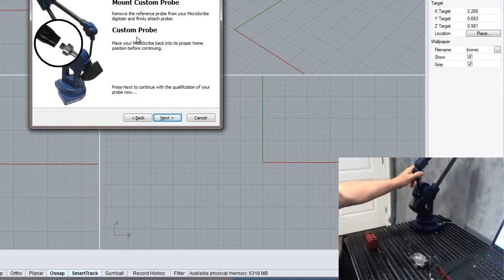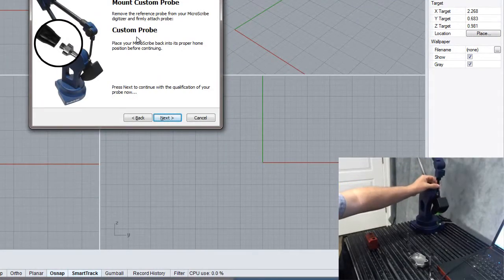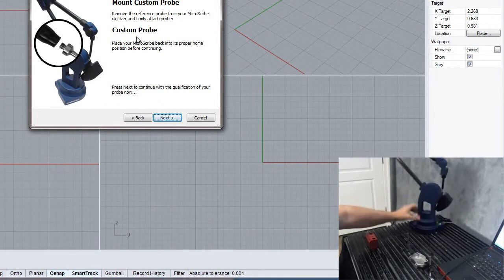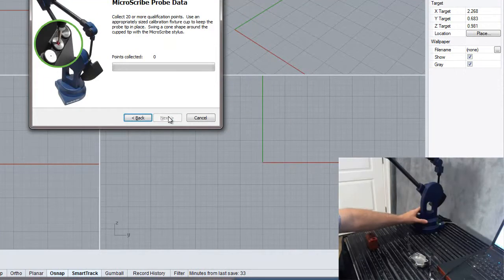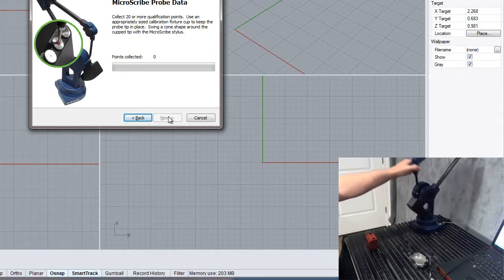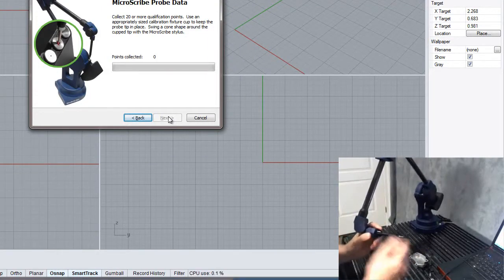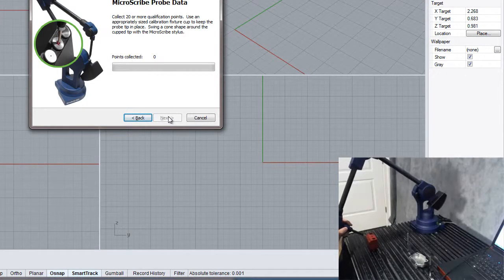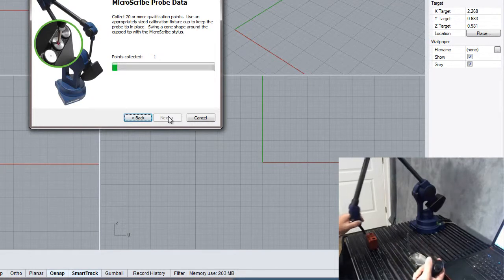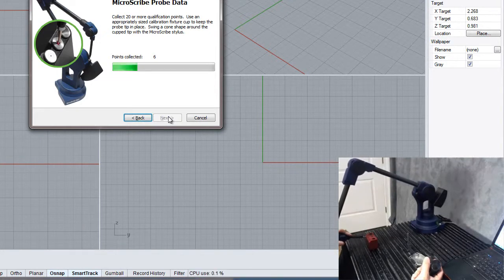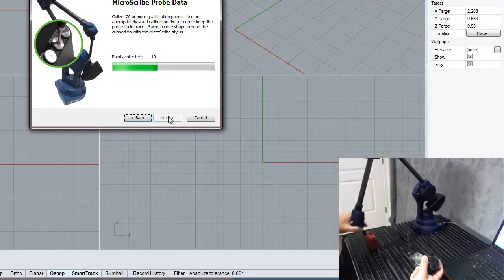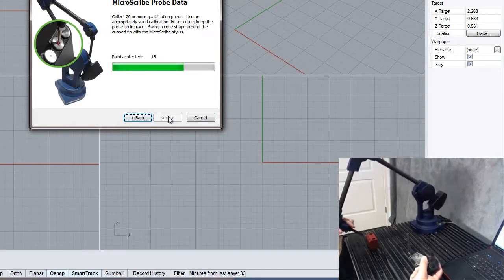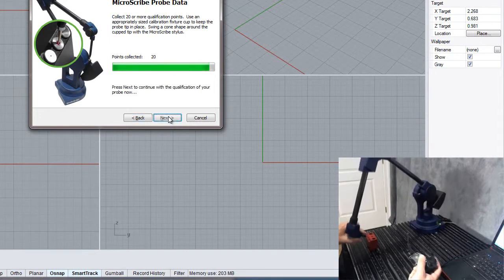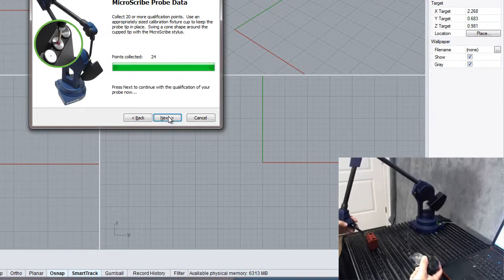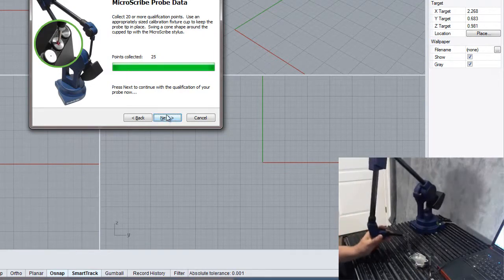It says place it into the home position once again, so we'll bring it back around. And again, because this is a 6DOF, we will home it, and we'll go ahead and press the next button. So the next thing it wants us to do is to pick up 20 points so that it can find the length difference in any axial deviation there may be in the probe itself. I've got a very small pinhole here on my calibration fixture, and I'll start collecting points. So using the hand trigger, I'll collect points by moving the arm and keeping that point still in one place on my calibration fixture. I want to take a series of 20 or more points. Now it's told me that we have enough points to do the calculation. So we'll go ahead and hit next.